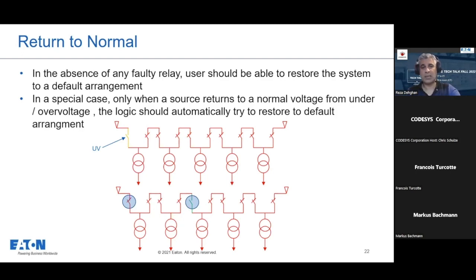So they wanted only, not for overcurrent cases, but only for under voltage and over voltage faults. If the first or last breakers are going back to normal voltage, they wanted the logic to automatically try to restore the system to a default arrangement. Next page.